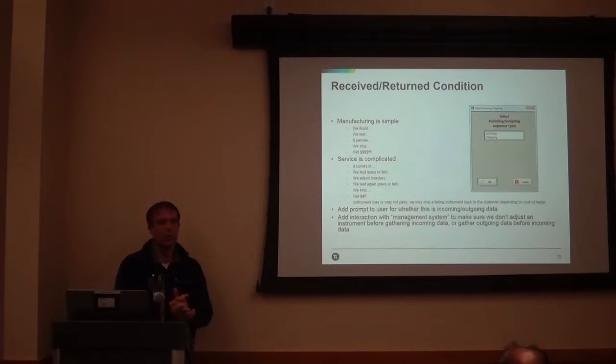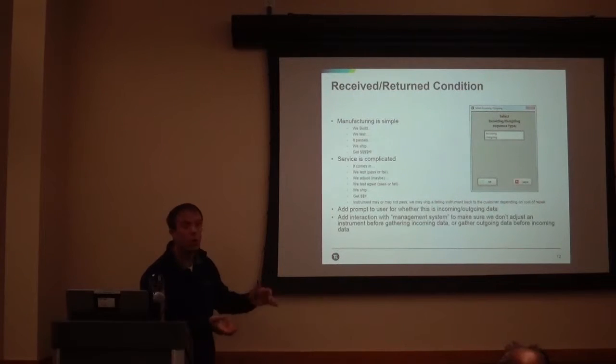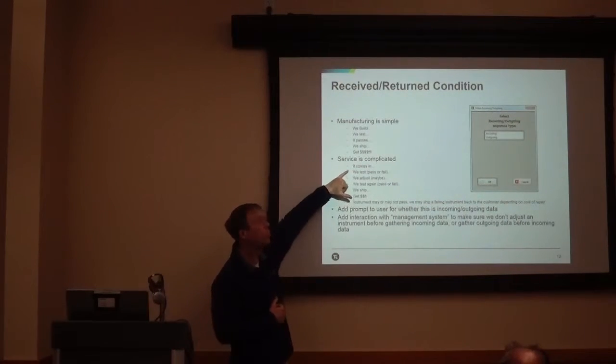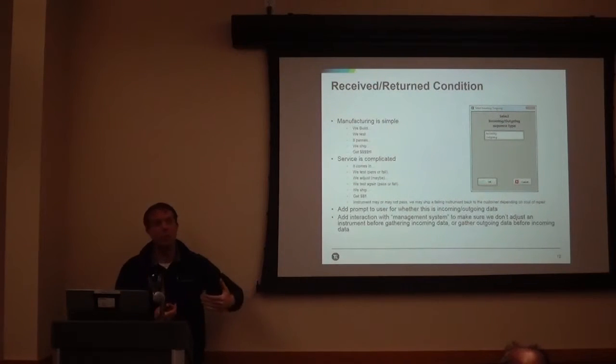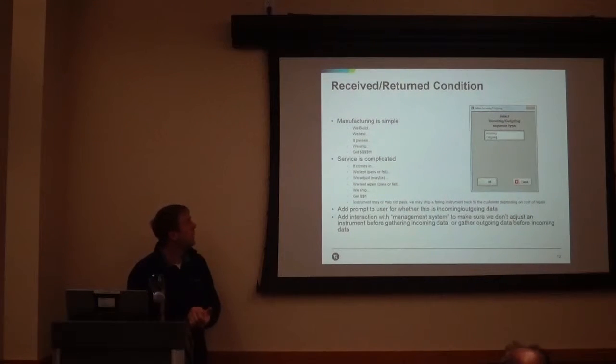Do you really want us to spend a gazillion dollars repairing it for you? And they say, no, we accept these failures, please ship it back to us in that condition and just properly note it on our data report. So we can ship back with failing results, and that's okay based off the customer. We have to let them know what the data was when it first showed up at our plant and as it left, and any adjustments we perform.